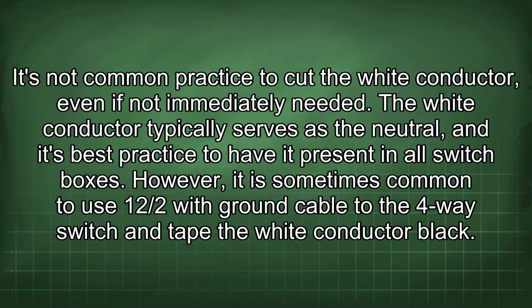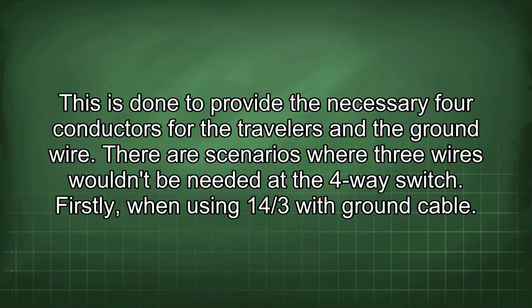It's not common practice to cut the white conductor, even if not immediately needed. The white conductor typically serves as the neutral, and it's best practice to have it present in all switch boxes. However, it is sometimes common to use 12/2 with ground cable to the 4-way switch and tape the white conductor black. This is done to provide the necessary 4 conductors for the travelers and the ground wire.